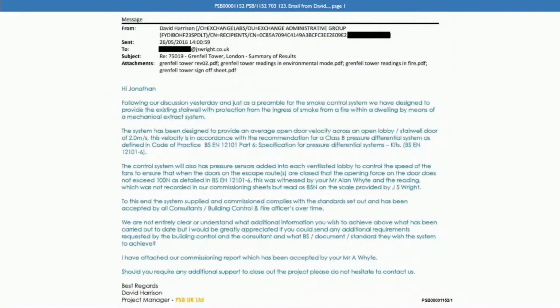Yes, let's look at some contemporaneous emails on this. If we go to PSB 401152, we can see an email from David Harrison of PSB to Jonathan Earle at JS Wright. It's dated the 26th of May 2016. And he says, Hi Jonathan, following our discussion yesterday and just as a preamble, for the smoke control system we have designed to provide the existing stairwell with protection from the ingress of smoke from a fire within a dwelling by means of a mechanical extract system. The system has been designed to provide an average open door velocity across an open stairwell door of 2 metres per second. This velocity is in accordance with the recommendation for a Class B pressure differential system as defined in Code of Practice 12101 Part 6.